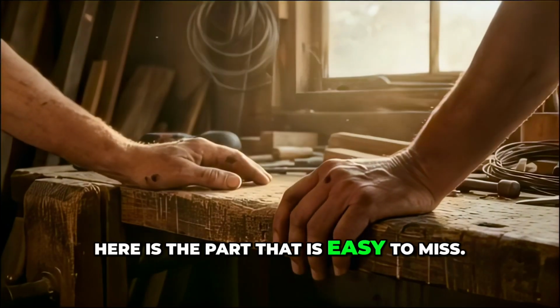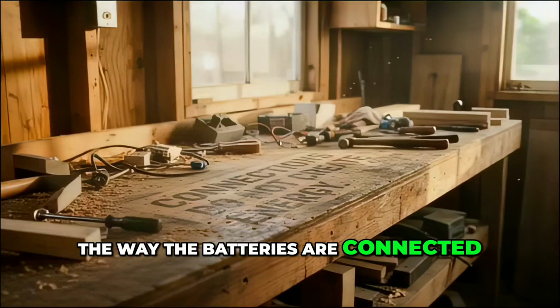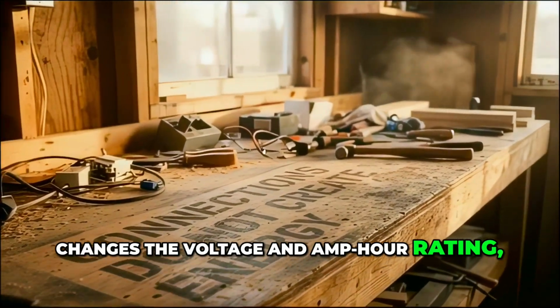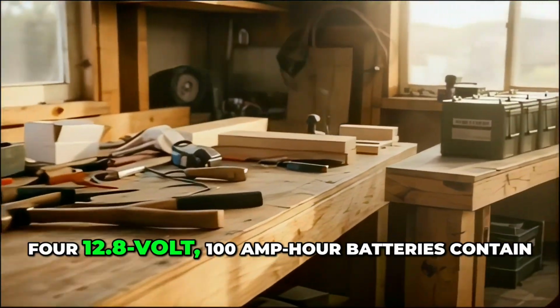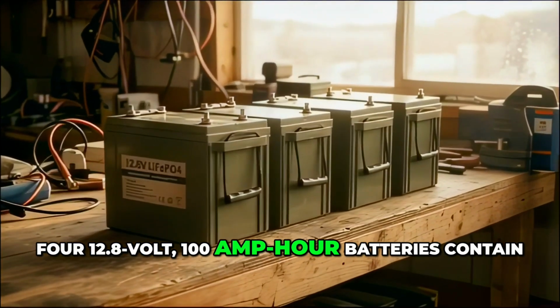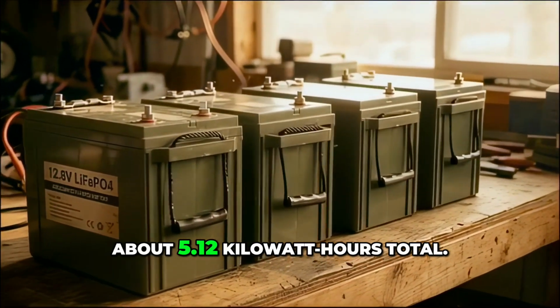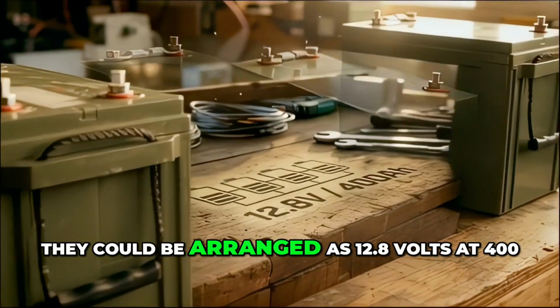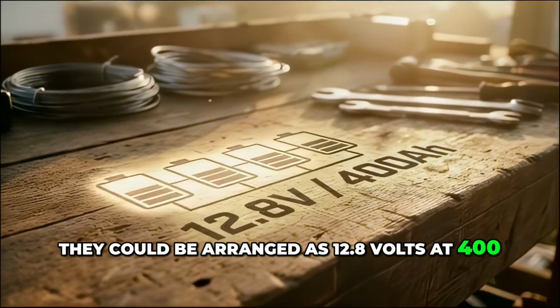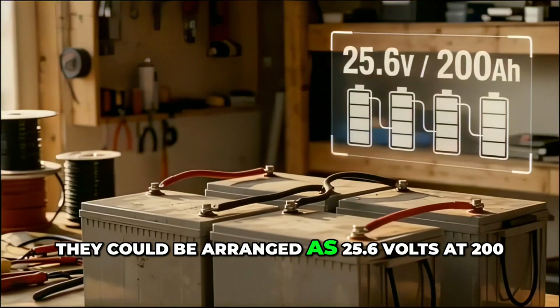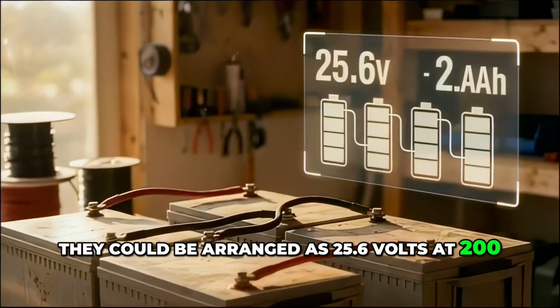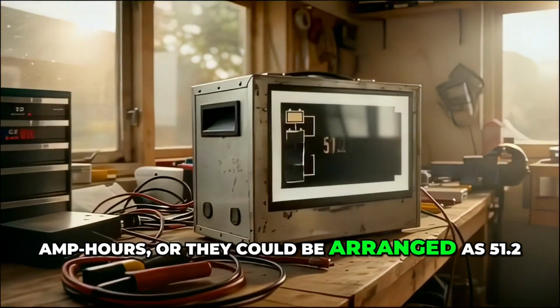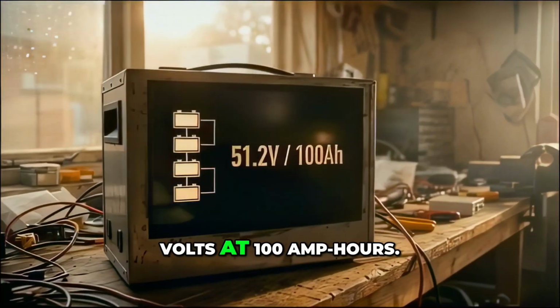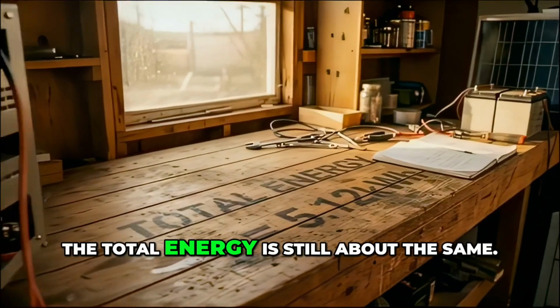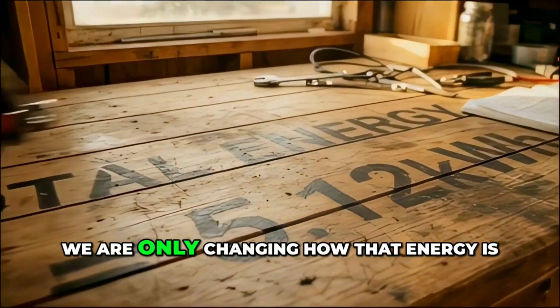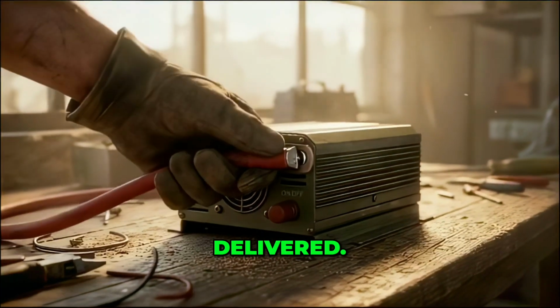Here is the part that is easy to miss. The way the batteries are connected changes the voltage and amp-hour rating, but it does not create more energy. 4 12.8-volt, 100 amp-hour batteries contain about 5.12 kilowatt-hours total. They could be arranged as 12.8 volts at 400 amp-hours. They could be arranged as 25.6 volts at 200 amp-hours. Or they could be arranged as 51.2 volts at 100 amp-hours. The total energy is still about the same. We are only changing how that energy is delivered.